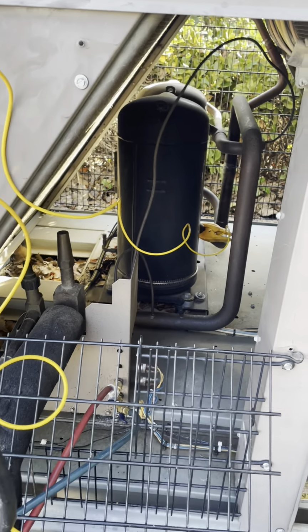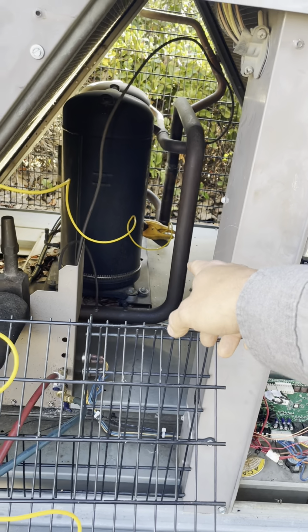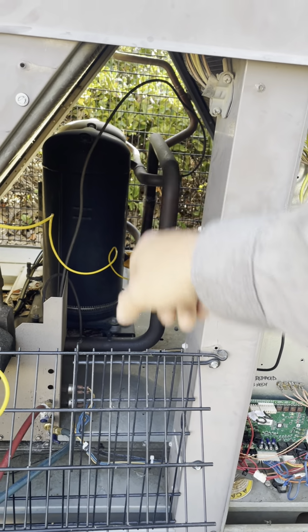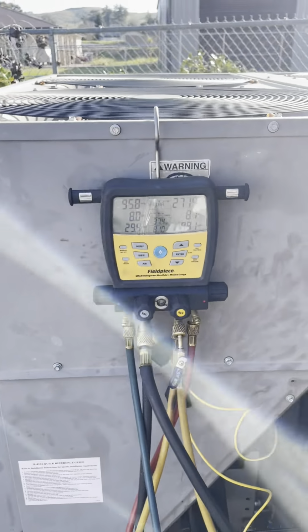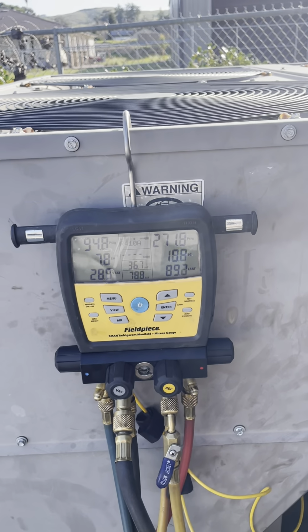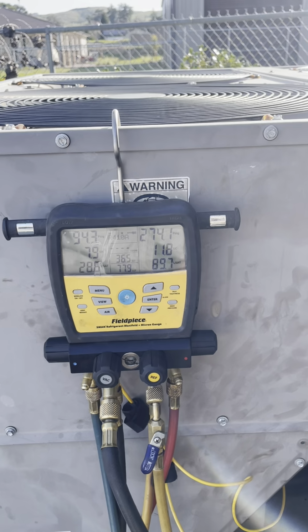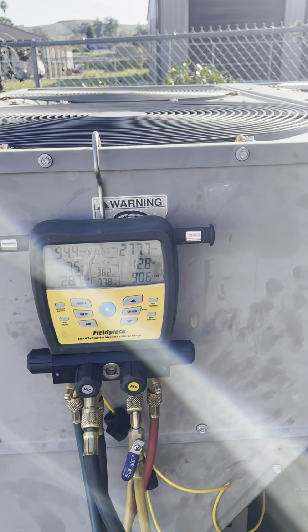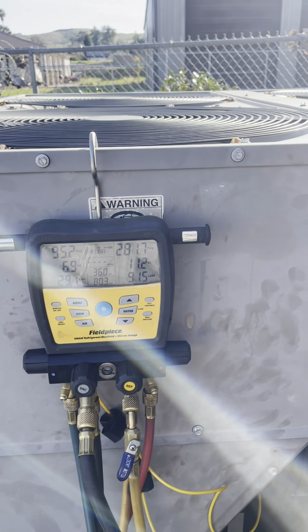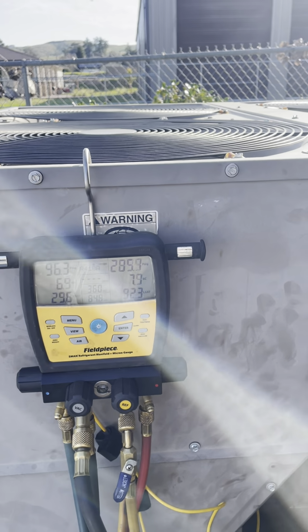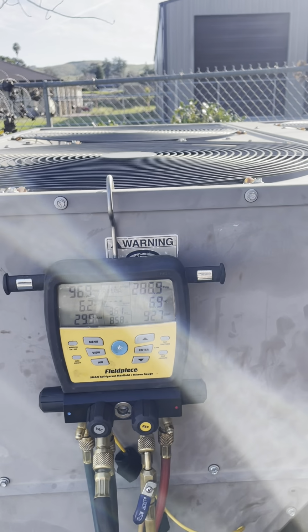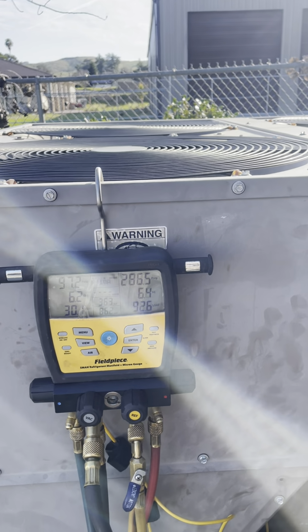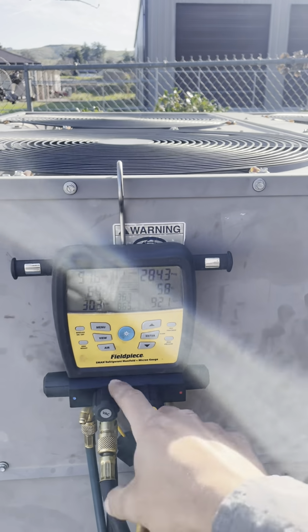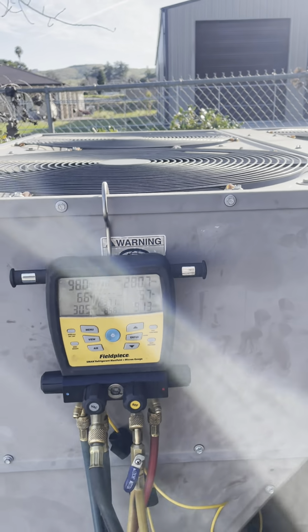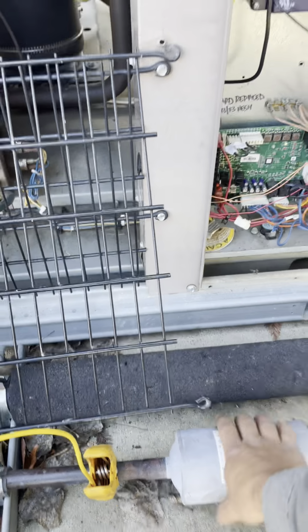Okay, I messed up earlier. That wasn't the suction line. I was hooked up to the discharge line, like an idiot. Whoopsie. But now I'm on the suction line. This thing is purring away. My space temp's about 72 degrees, and I'm running a lot of cooling right now, so this thing is doing too much. It's probably going to freeze up. My vapor saturation is dropping below 32 degrees. I'm going to go check that supply air temperature again.